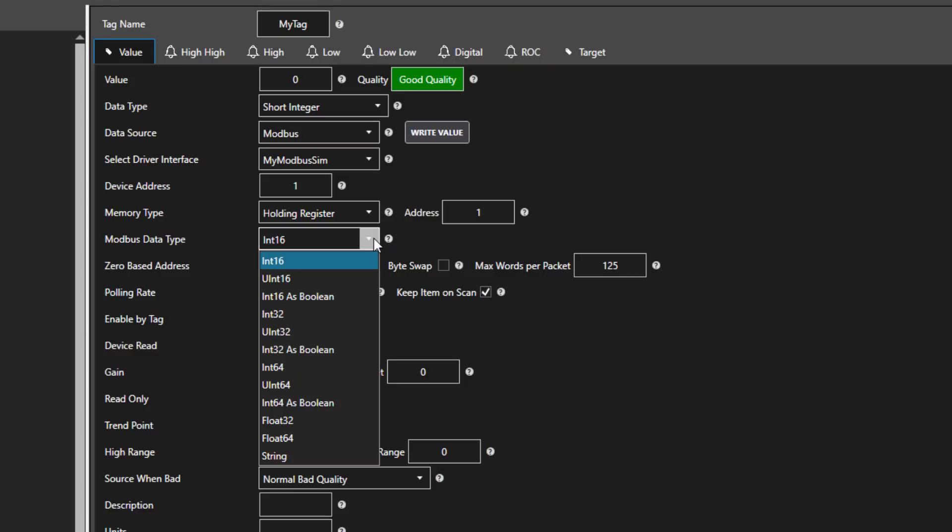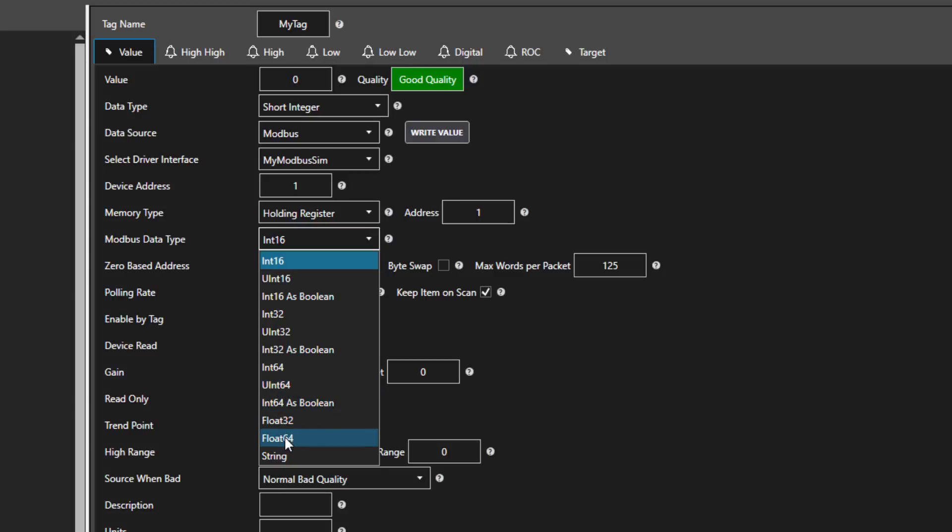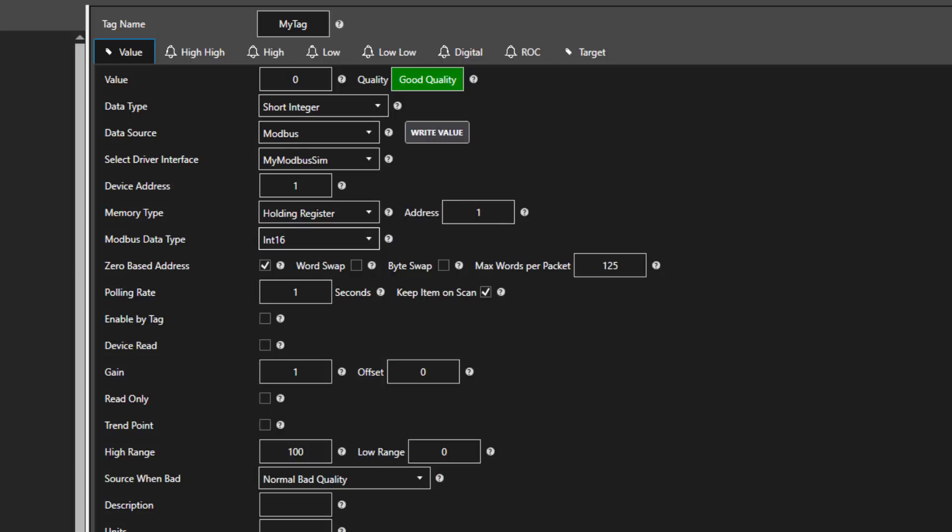Here we can specify the Modbus data type. It defaults to a 16-bit integer. You can also use unsigned integers of 16, 32, and 64 bits. You can use 32-bit or 64-bit floats. If you use a float64, that would span 4 words from a Modbus device. You can also specify it as a string.